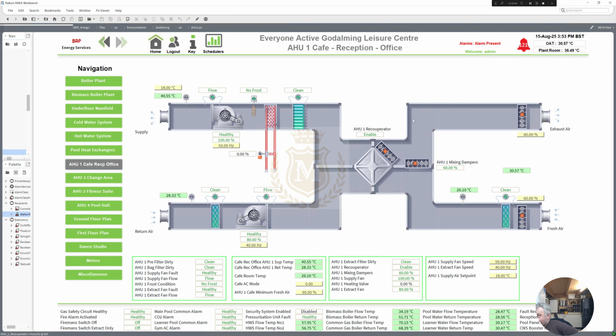That's enabled at the moment. What temperature? It's 30.57 according to that outside. So why are you at 60% and why are you recuperating? There's no chilled on there, there's only hot water. That's the reason why. Because it's too hot outside.